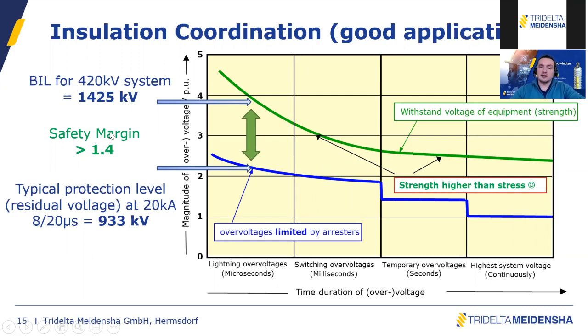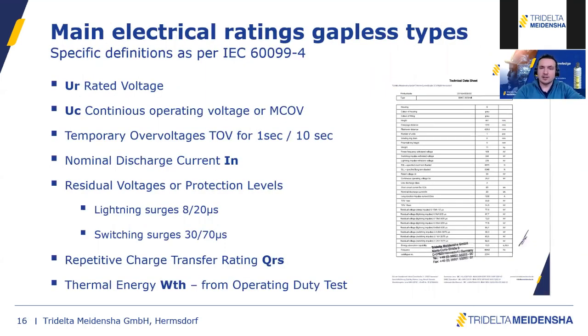So then you're safe. This is what you want to achieve. This is the key. Once you understand that you always need your residual voltage to be below the BIL of the system, then you understood everything. We don't have to go further. It could be obvious for many people, but it's still misunderstood, because this residual voltage could also be used to go further. This is what we discussed in the last webinar about insulation withstand, so we'll not develop it too much unless you have questions at the end.